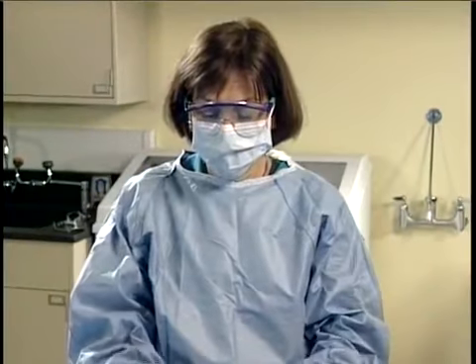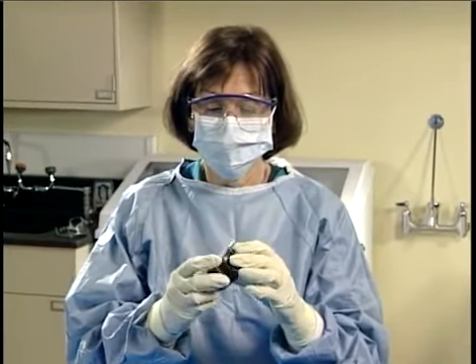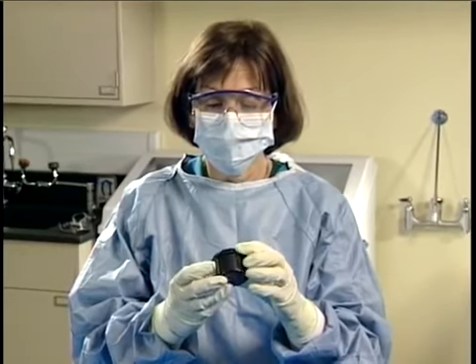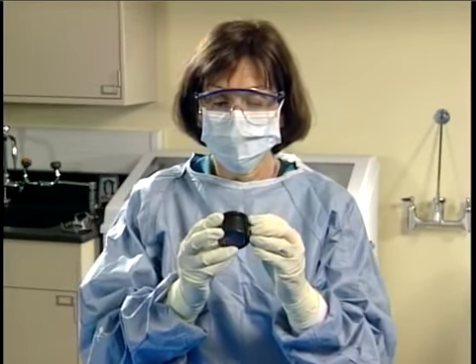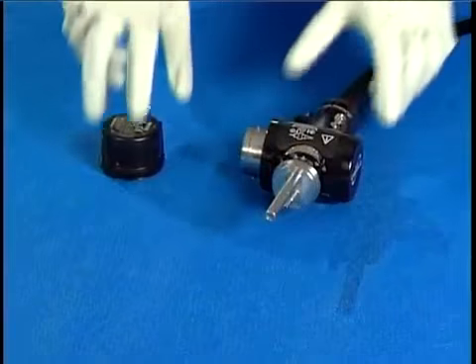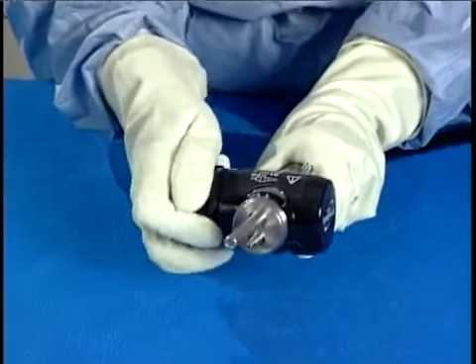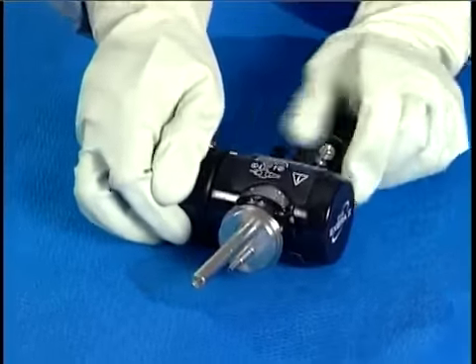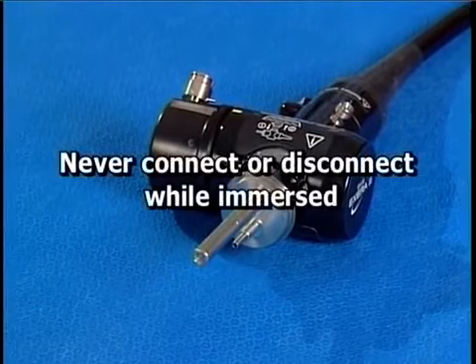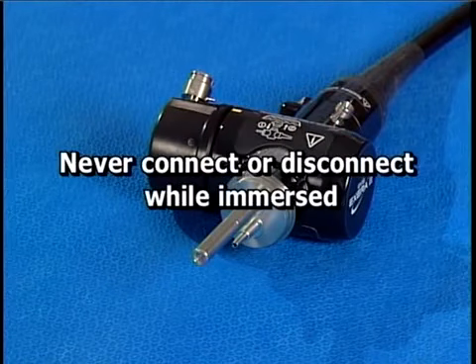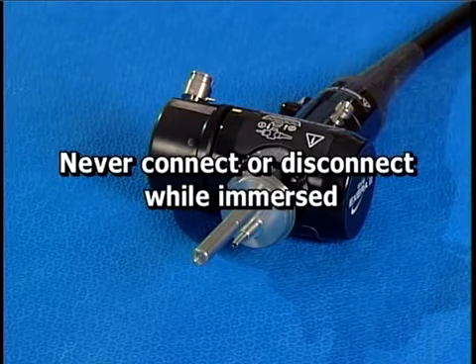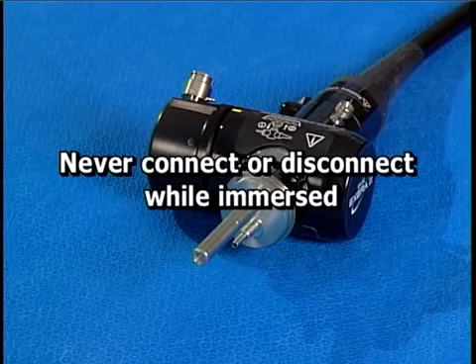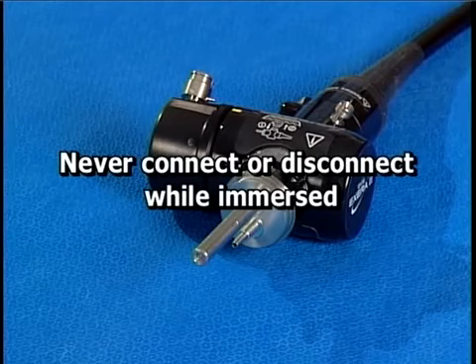The following step should be performed prior to immersing your endoscope in any fluid. Visually inspect the water-resistant cap for damage. If it is damaged or wet, use another cap. Attach the water-resistant cap to the endoscope. Remember, never connect or disconnect the water-resistant cap while the cap or the endoscope is immersed. Doing so will damage the endoscope.